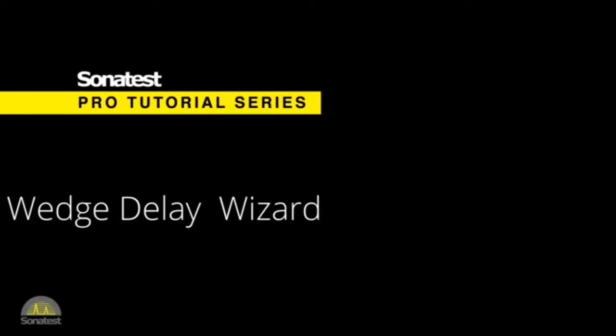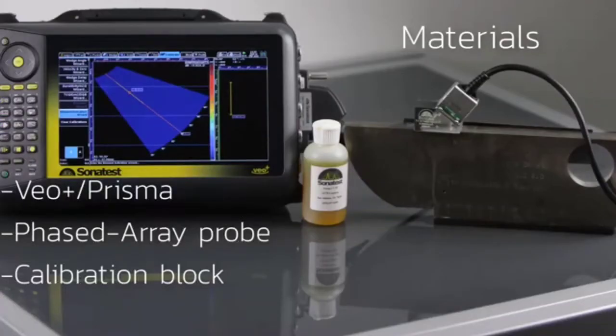In the velocity and zero calibration, we settled the velocity for one angle only. The velocity of sound in an isotropic material remains constant for all angles. The zero, however, changes according to its related angle. This calibration wizard calibrates the zero for all angles. The same equipment as the velocity calibration is required.